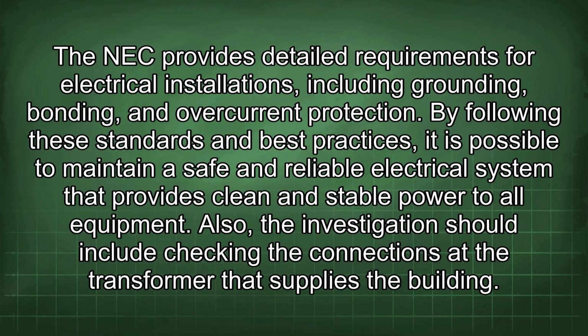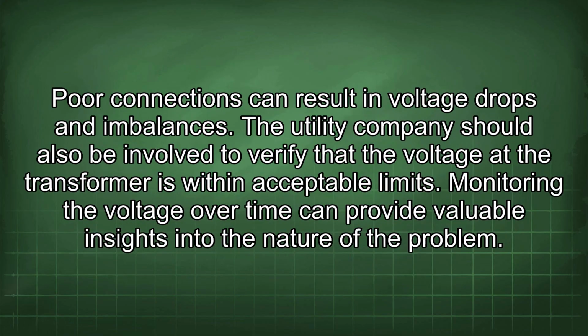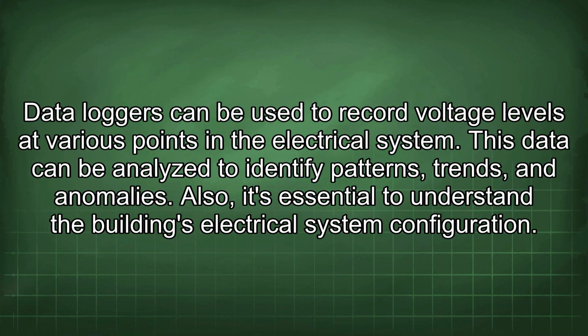Also, the investigation should include checking the connections at the transformer that supplies the building. Poor connections can result in voltage drops and imbalances. The utility company should also be involved to verify that the voltage at the transformer is within acceptable limits. Monitoring the voltage over time can provide valuable insights into the nature of the problem. Data loggers can be used to record voltage levels at various points in the electrical system. This data can be analyzed to identify patterns, trends, and anomalies.